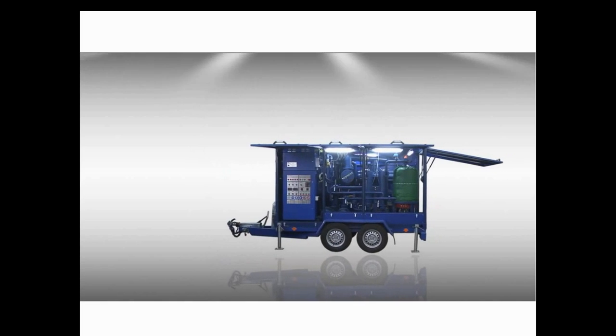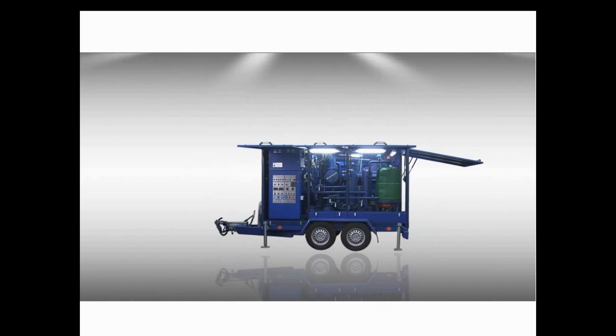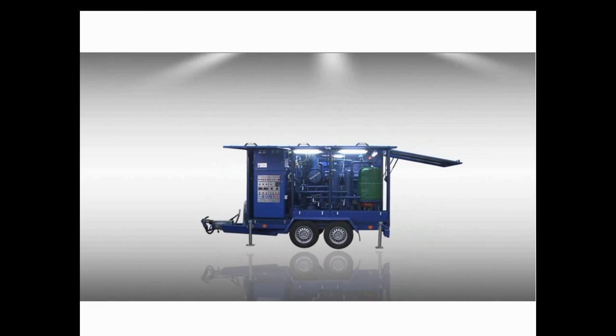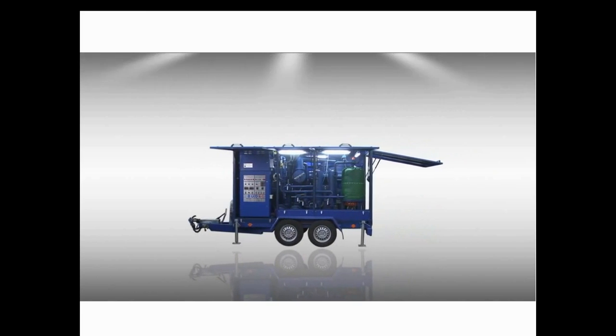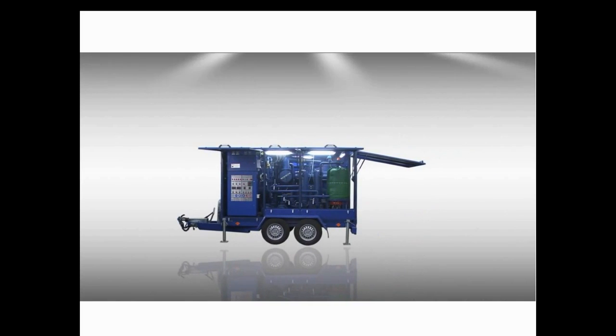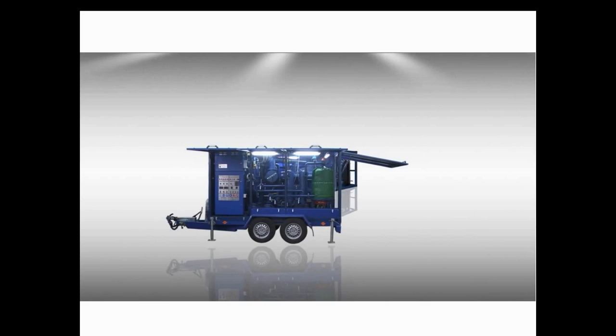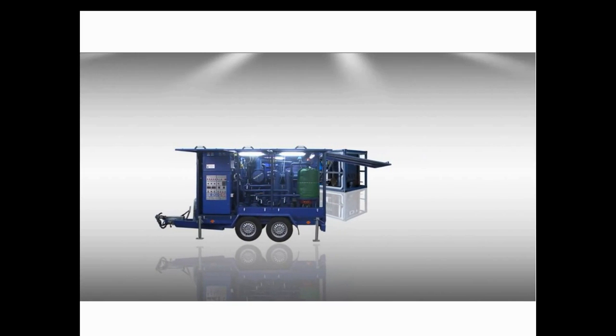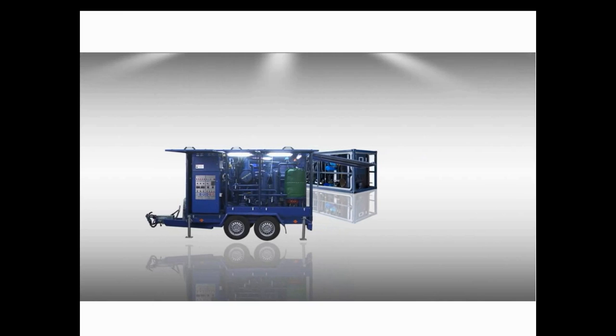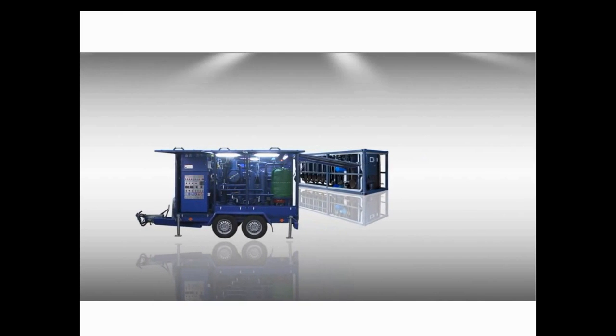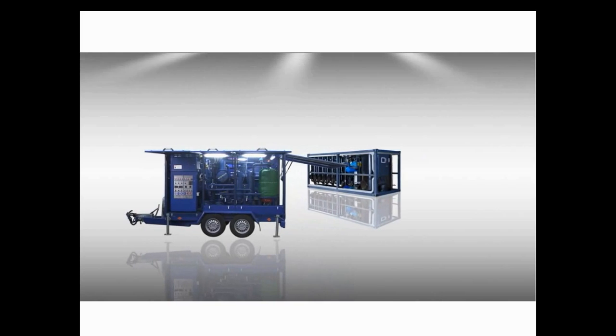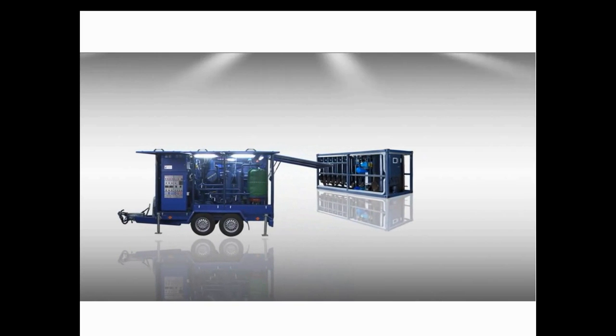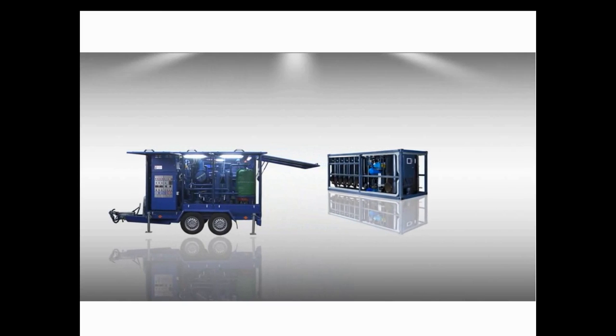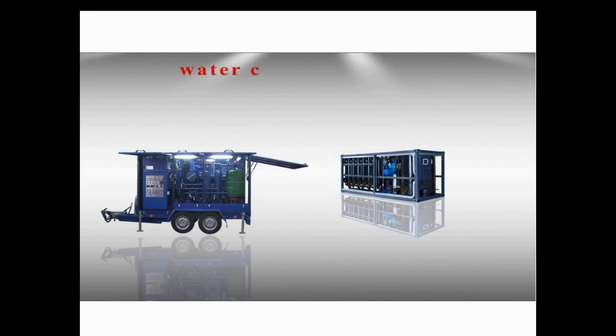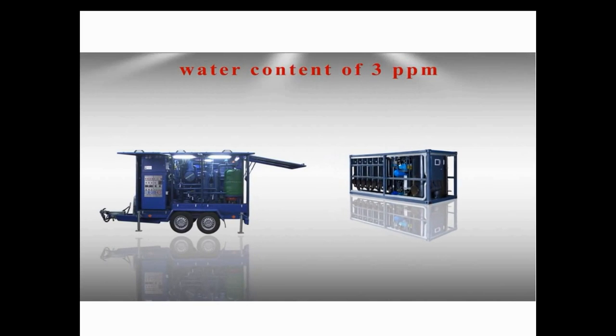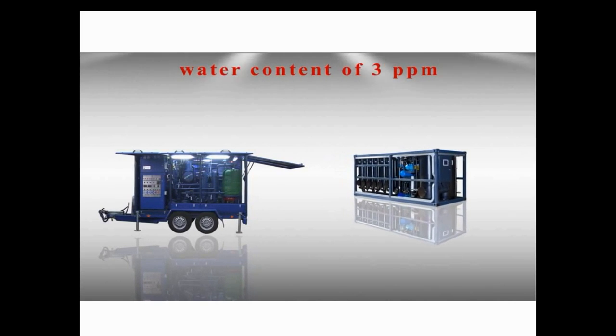Now, I'd like to bring you right to purification or oil degassing talk to show the difference between purification and regeneration. Please remember that regeneration does not replace purification, as both of them are very important for transformer maintenance. Just to refresh your mind, purification means removal of water, gases, and sludge from transformer oil. By the way, this is what GlobeCore oil purification plants can perfectly cope with.